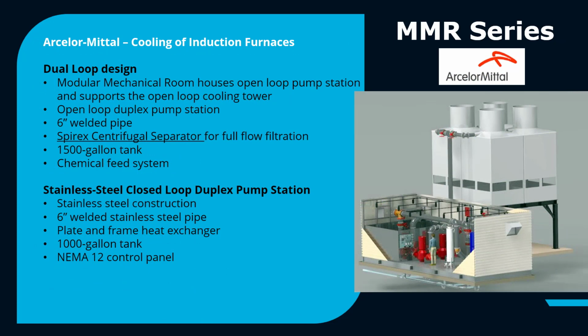Another MMR example takes place in the process world at ArcelorMittal. This application is for the cooling of induction furnaces. It's a dual loop design that involves stainless steel construction. The modular mechanical room houses an open loop pump station and supports open loop cooling towers. An open loop duplex pump station is included.